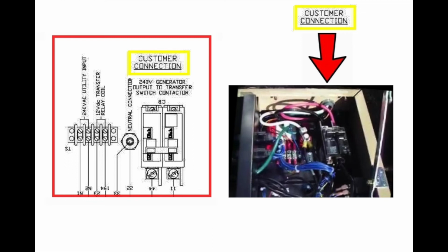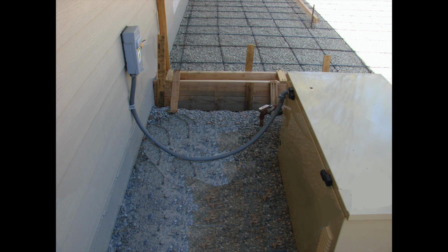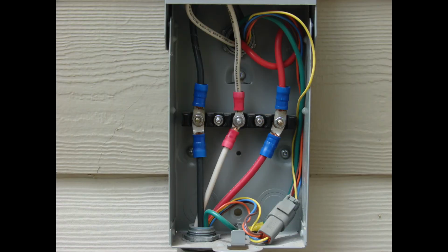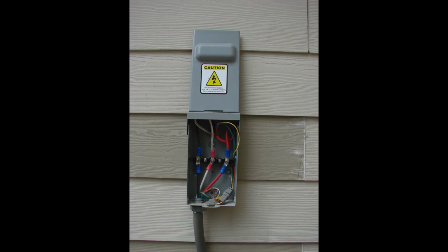The ground, of course, has its own ground terminal. The neutral wire has a neutral lug as well. And then the two lines for the 240 volt coming out of the generator go directly to the circuit breaker in this case. In some cases, you will have a junction box that is mounted on the outside of the building before the flex actually goes to the generator.